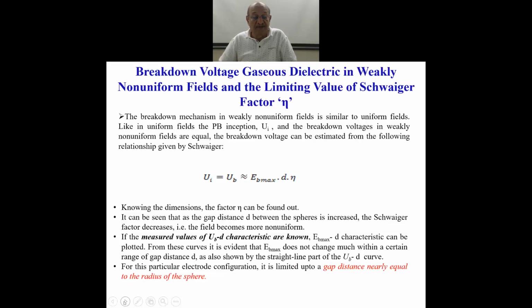So when we are still in weakly non-uniform field configuration, it has been experimentally verified and also analytically verified. The breakdown strength can be calculated or estimated with the help of an analytical formula using the Schweiger factor, eta. The breakdown mechanism in weakly non-uniform fields is similar to uniform fields.